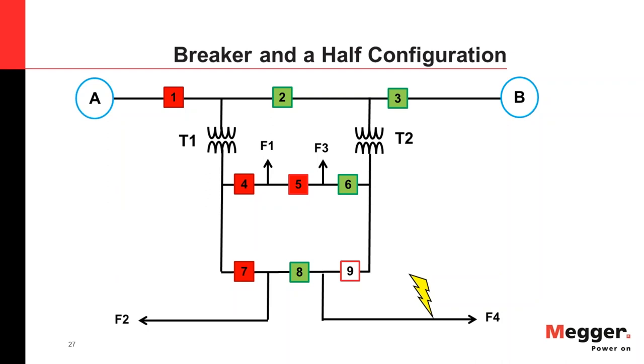Another question about the breaker-and-a-half configuration: wouldn't Breaker 2 usually be open since otherwise Sources A and B would continuously feed together? Yes, that is correct — Breaker 2 should be open in that diagram. That was an error in the slide.